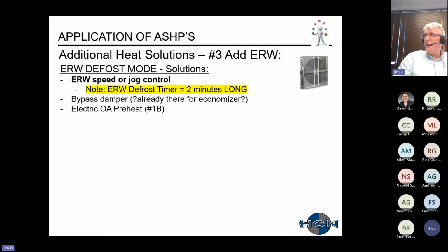Or if you have a VFD on your unit, what you're basically doing is slowing down the wheel, you're reducing your heat transfer. You're essentially using the return air to warm up the media of the wheel. Other solutions for the defrost mode: you could implement a bypass damper. You might already have it there for economizer mode, and then you could add an electric preheat to raise your outside air temperature above that dew point temperature.